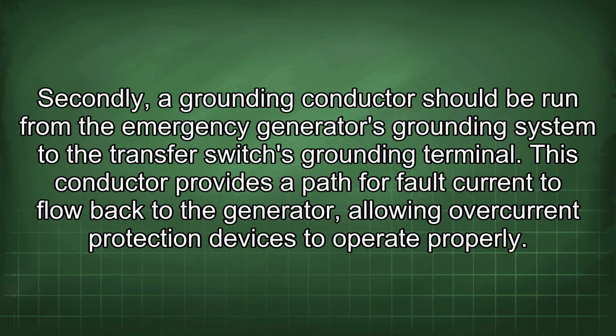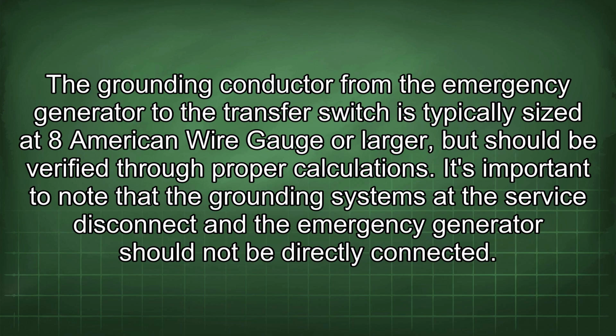Secondly, a grounding conductor should be run from the emergency generator's grounding system to the transfer switch's grounding terminal. This conductor provides a path for fault current to flow back to the generator, allowing overcurrent protection devices to operate properly. The grounding conductor from the emergency generator to the transfer switch is typically sized at 8 American wire gauge or larger, but should be verified through proper calculations.